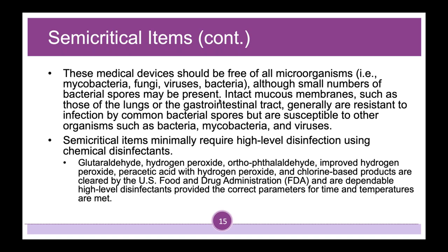Semi-critical items minimally require high-level disinfection using chemical disinfectants. That's going to be glutaraldehyde, hydrogen peroxide, ortho-phthalaldehyde, improved hydrogen peroxide, peracetic acid with hydrogen peroxide, and chlorine-based products that are cleared by the U.S. Food and Drug Administration and are dependable high-level disinfectants, provided the correct parameters for time and temperature are met.